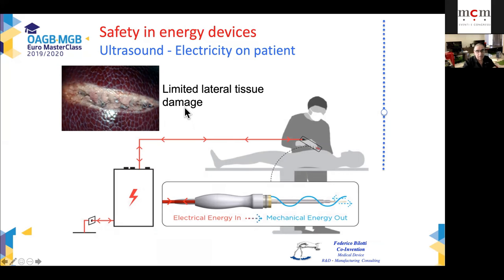The ultrasound works differently than any other device because there's no electricity applied to the patient. What the instrument does is apply vibration of one of the two jaws. And this vibration is the mechanical transformation of the electricity that the generator receives. Describing what happens in the handle of the ultrasound device: piezoelectric rings increase and decrease their volume and their size, and this causes them to bang against each other. This banging is transformed into waves. These waves are mechanical waves and cause the vibration of one of the two jaws.